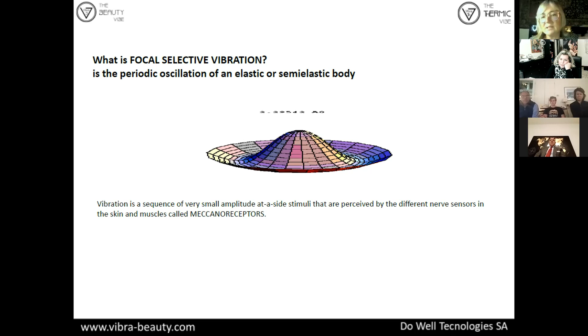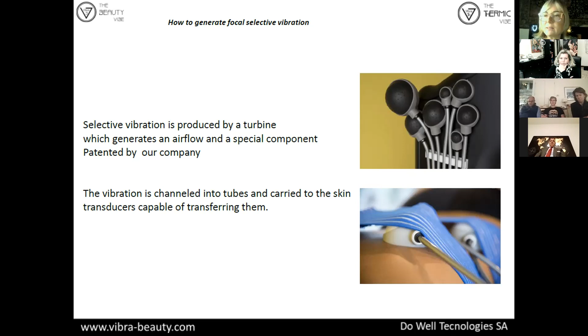It's produced in our device by a turbine inside the machine that generates airflow, together with a very special component that is patented by our company. This vibration is channeled into the tubes you see on the screen. We have 7 on the left and 7 on the right, and they are carried to the skin transducers. The transducer is fixed on the skin by these elastic bands, okay? So vibration is made by air, and that is the first concept, by air. It is natural. Air is natural, and that is one of the main strength points of Vibra.